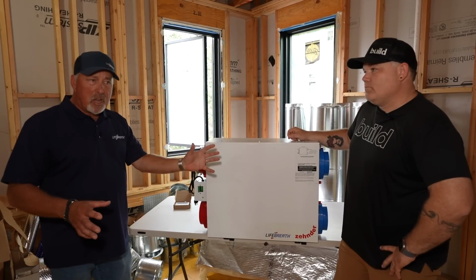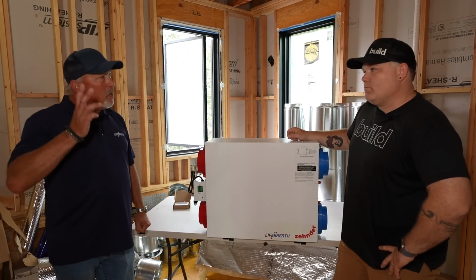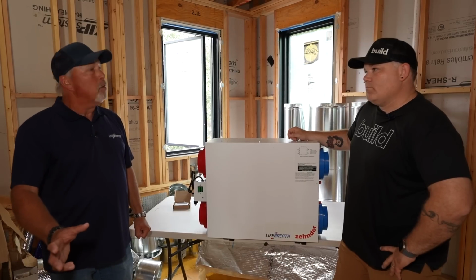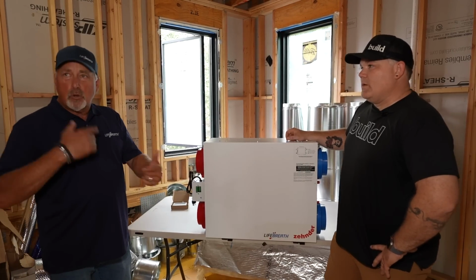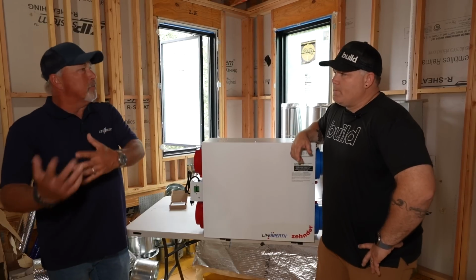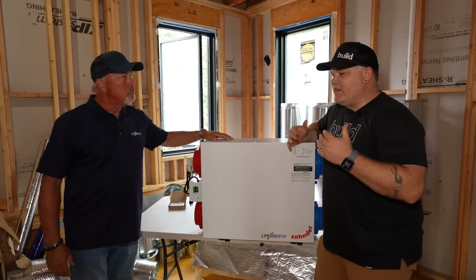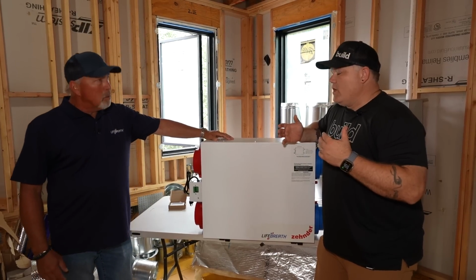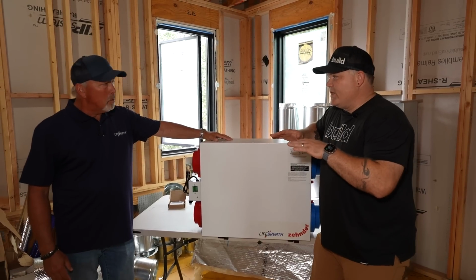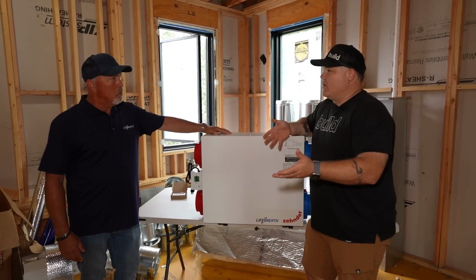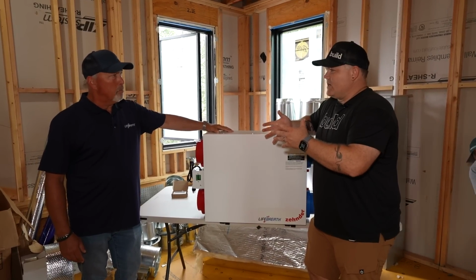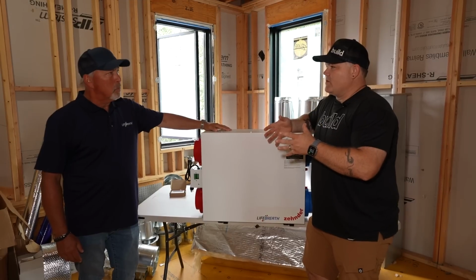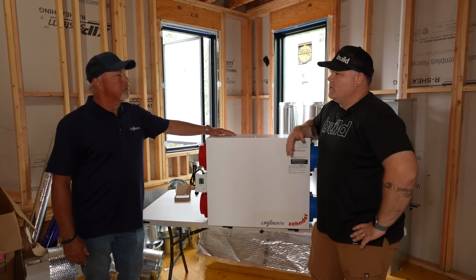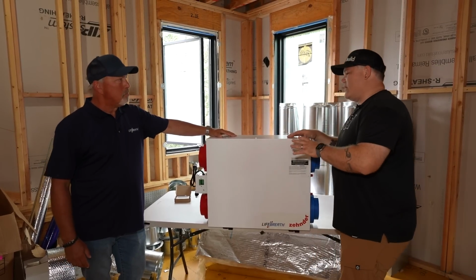We're just going to take stale air out of the return air and inject fresh air back into the return air of the system. It then goes through the air handler and gets delivered to the house. So if any conditioning needs to be done with that air, whether temperature or humidity, it's going through the air handler, and you're utilizing the ducting system and the air handler to push this throughout the house? Correct.